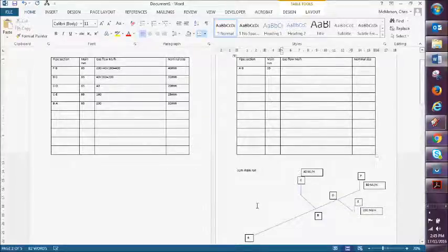So you've got to think of it in real life terms. This bit of pipe, this section A to B, needs to be big enough to carry enough gas to all the rest of the appliances in the house. It's 320, which is going to be 40 plus 200 plus 80, so 320.